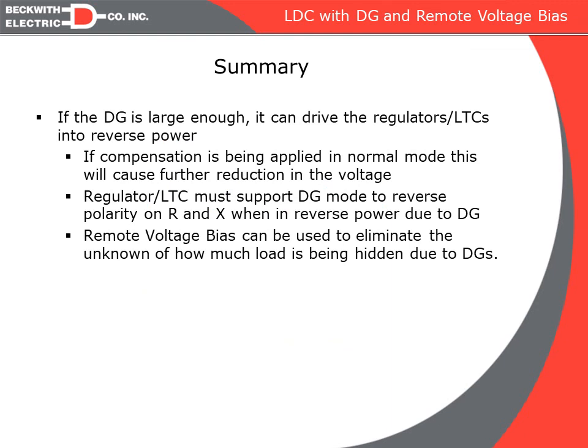In summary, if DG is large enough it can drive regulators into reverse power. Even when not in reverse power, traditional line drop compensation will undercompensate because the DG hides load current from the regulator's CTs. Due to the dynamic, rapidly changing output of DG sources such as solar and wind, the most accurate approach is remote voltage bias — actually monitoring the end-of-line voltage and calculating real-time voltage drop, rather than estimating from load conditions alone.